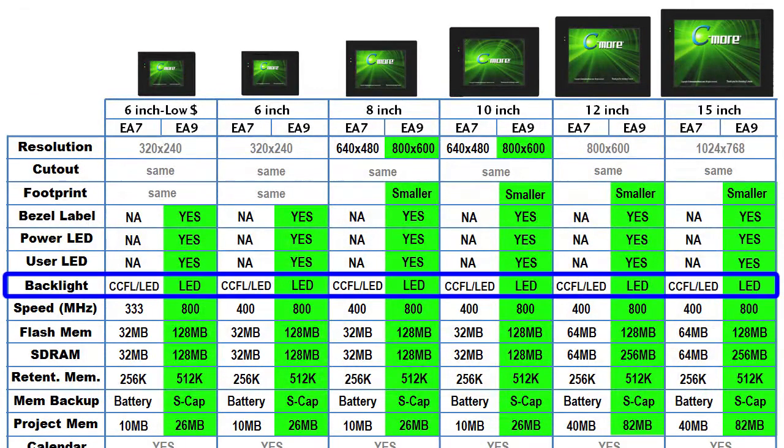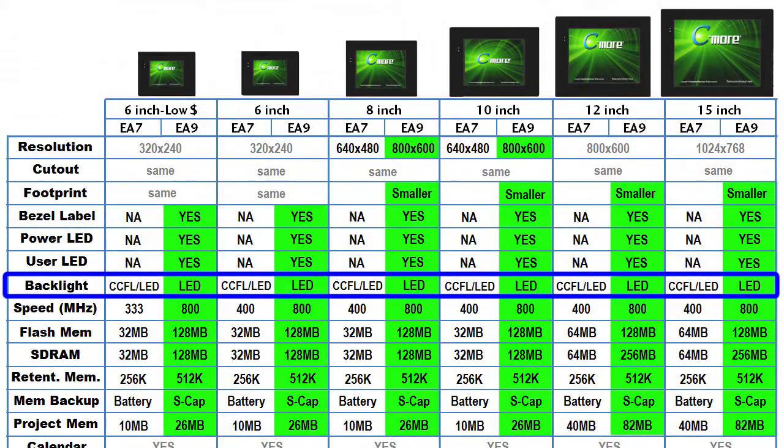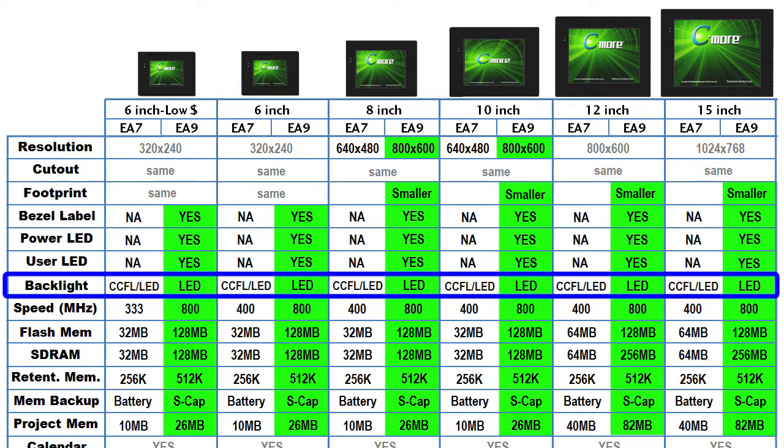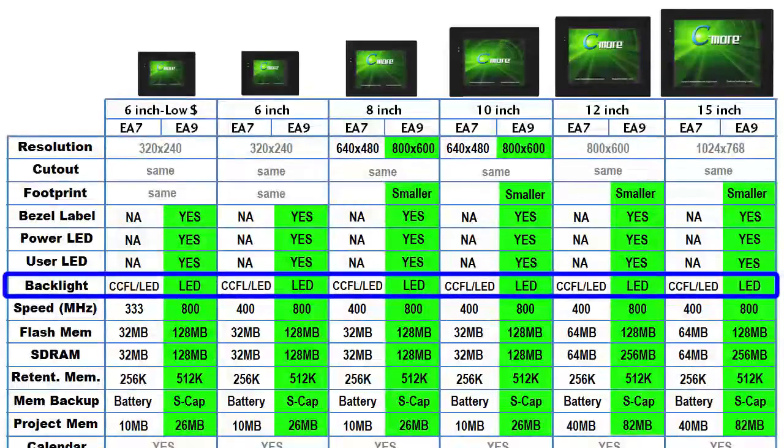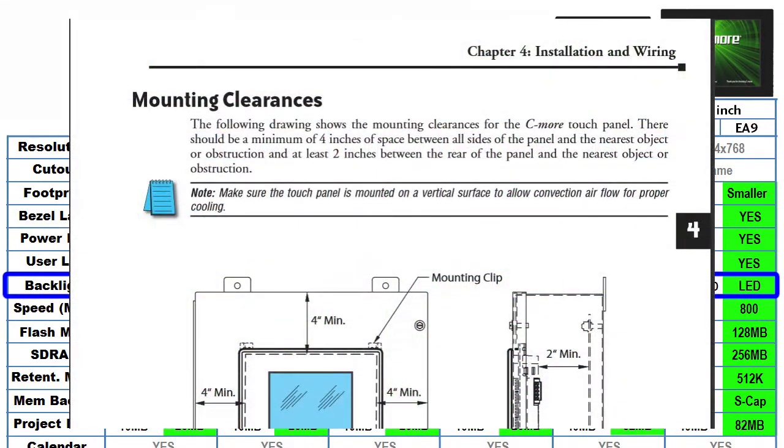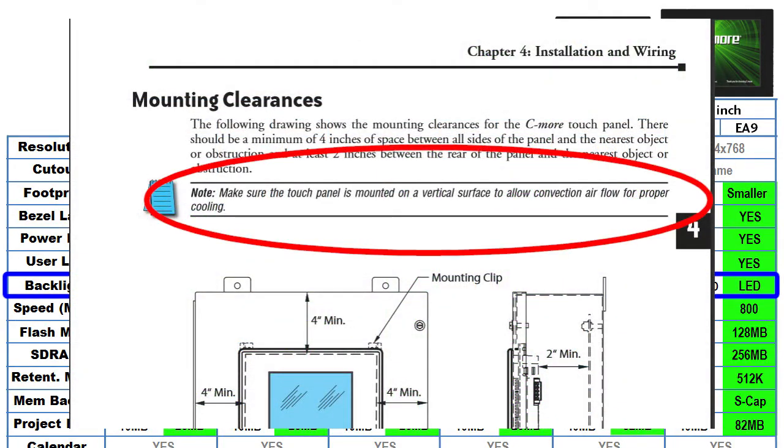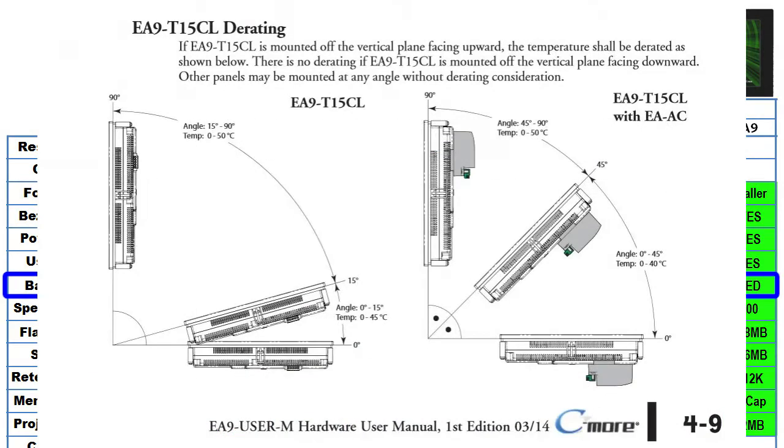The new C-mores come with permanent LED backlighting – no more taking the unit apart to replace the cold cathode fluorescent lamps. And since the CCFL power supply is gone, you no longer have to worry about heat dissipation when mounting the C-more. The original units had to be mounted vertically to ensure proper ventilation. The new EA9 panels can be mounted at just about any angle.